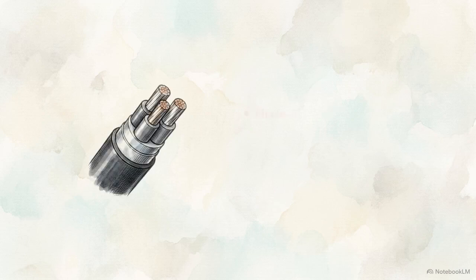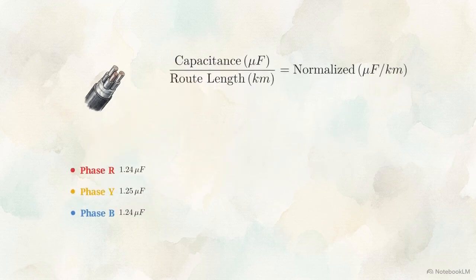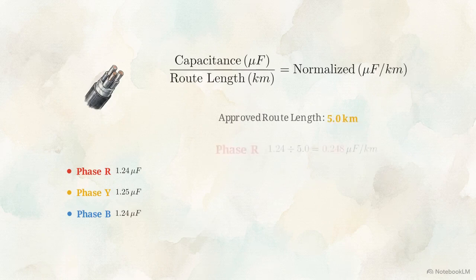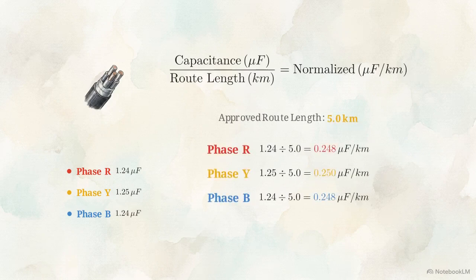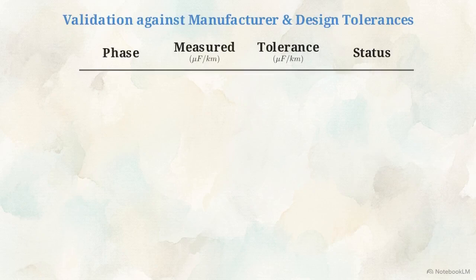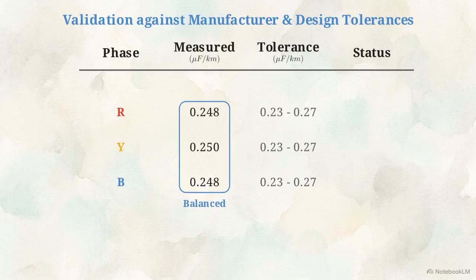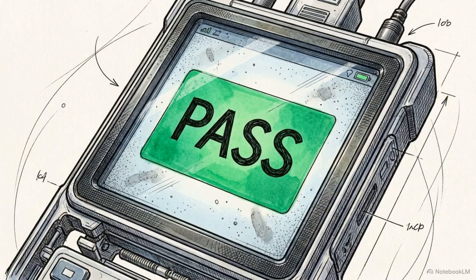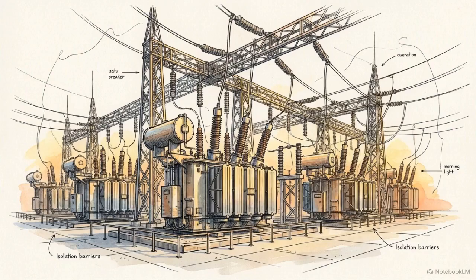Using these identical phase conductor configurations, technicians measure the circuit capacitance. The raw data is converted into microfarads per kilometer using the approved route length and compared directly against manufacturer datasheets and design tolerances to locate severe phase imbalances. Establishing uncompromised phase identity and proving foundational dielectric strength are absolute prerequisites. The grid cannot be subjected to extreme high-voltage stressors until these base measurements pass perfectly.